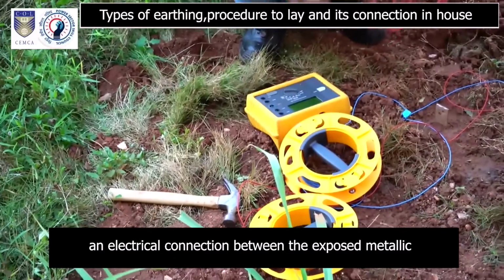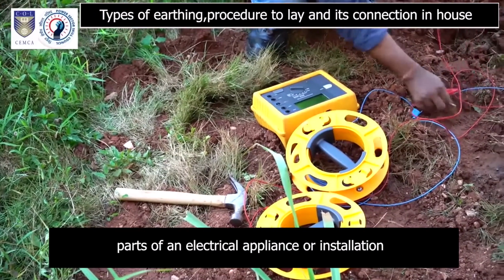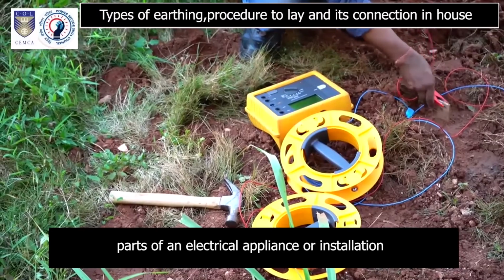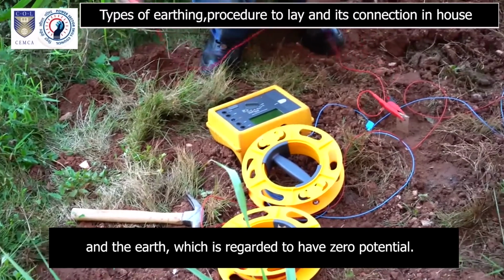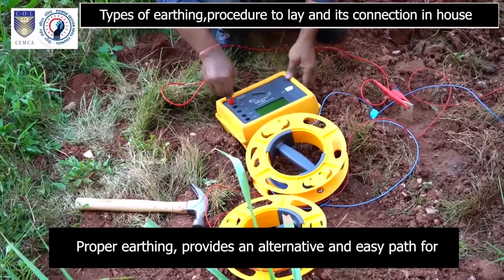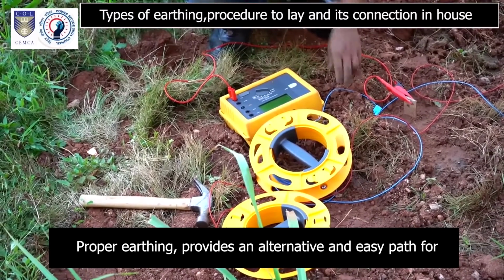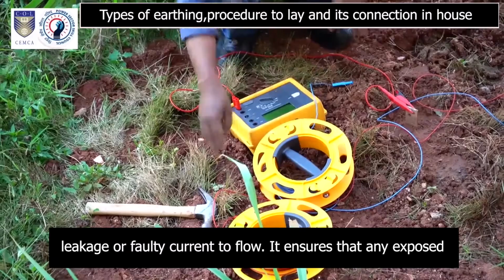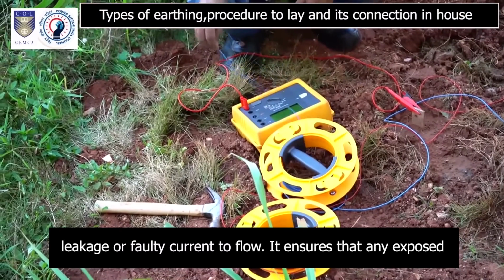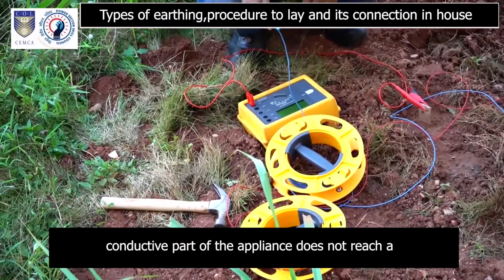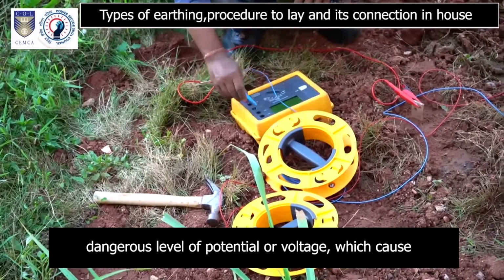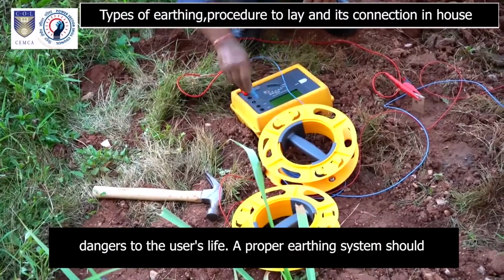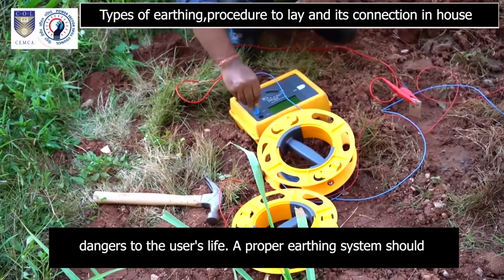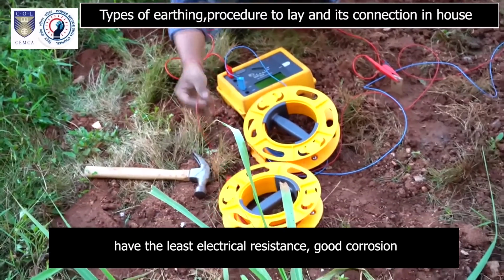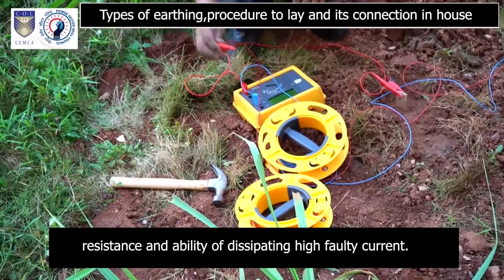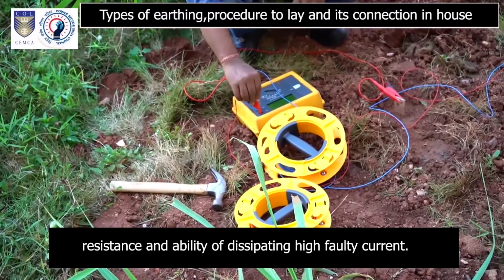It is an electrical connection between the exposed metallic parts of an electrical appliance or installation and the earth, which is regarded to have zero potential. Proper earthing provides an alternative and easy path for leakage or faulty current to flow. It ensures that any exposed conductive part of the appliance does not reach a dangerous level of potential or voltage, which causes dangers to the user's life. A proper earthing system should have the least electrical resistance, good corrosion resistance, and ability of dissipating high fault current.